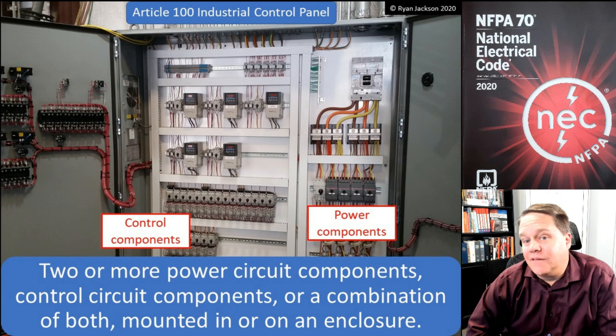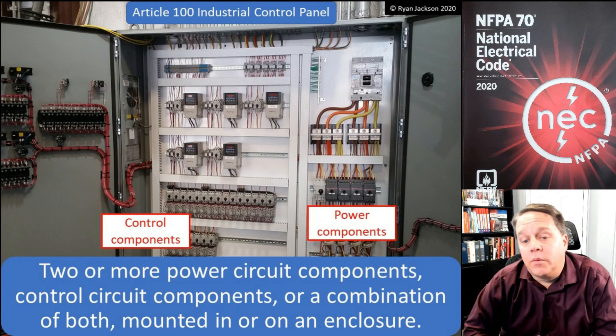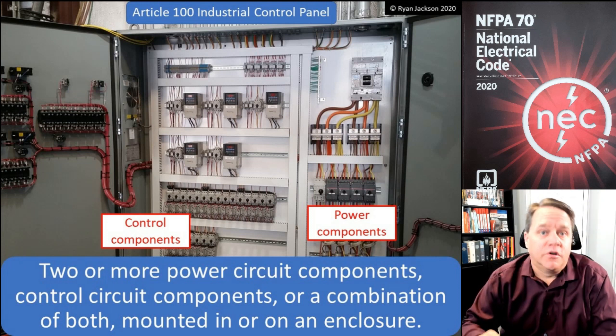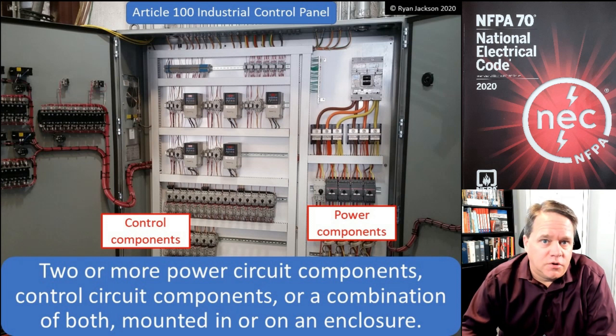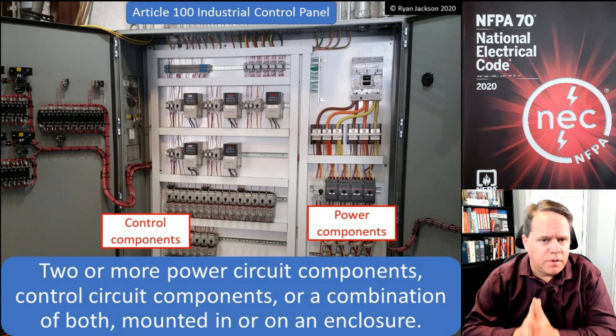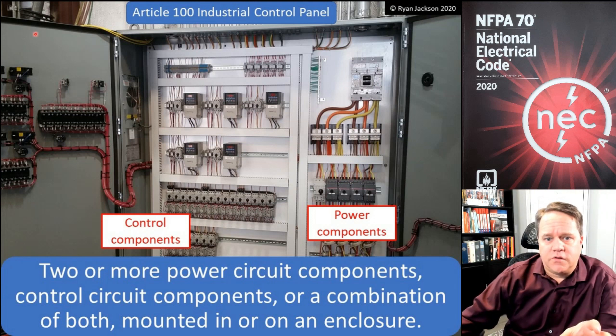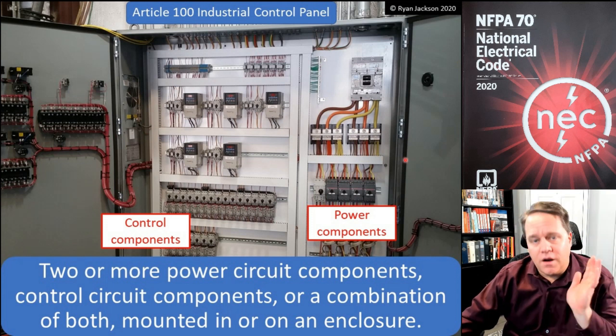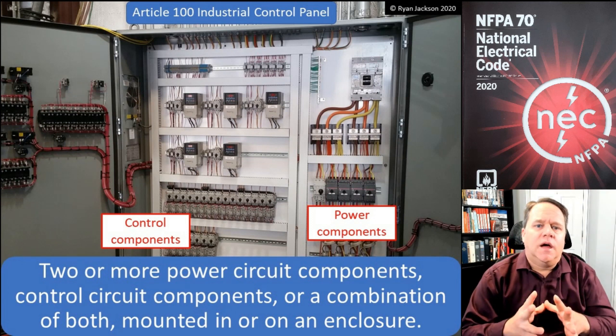Next up we have 'industrial control panel' here in Article 100. This is two or more circuit power circuit components, control circuit components, or a combination of both, mounted in or on an enclosure. Looking at the photograph here, this certainly meets that definition — we have an enclosure, control components on the left, and power components on the right. That is definitely an industrial control panel.